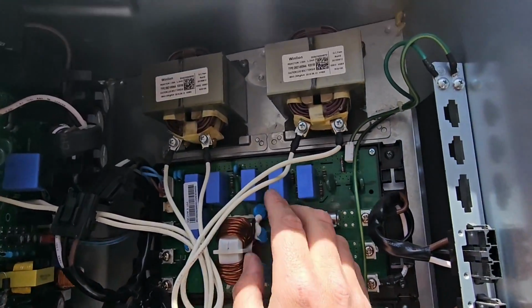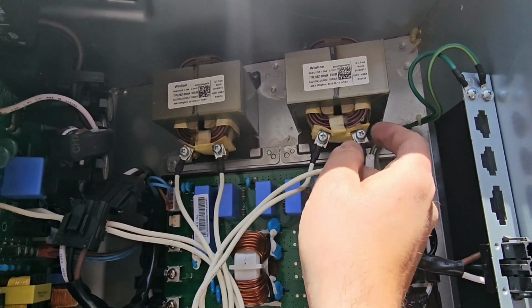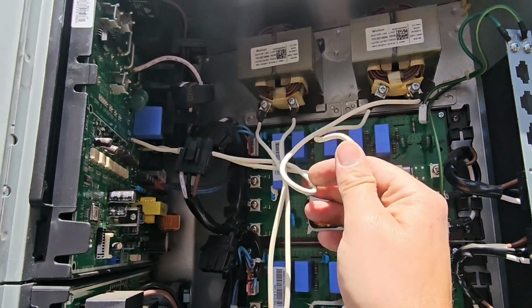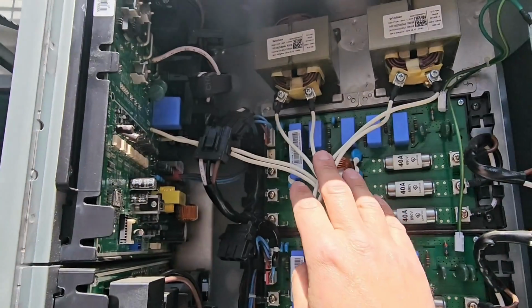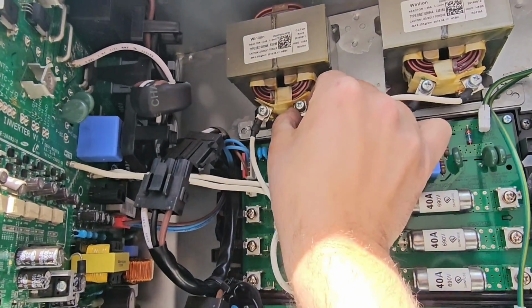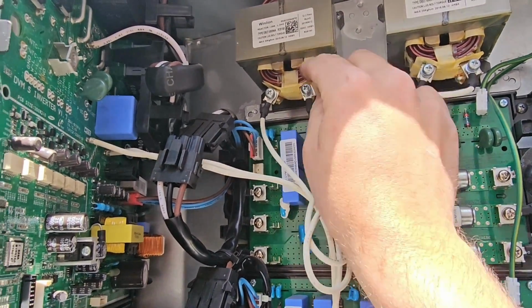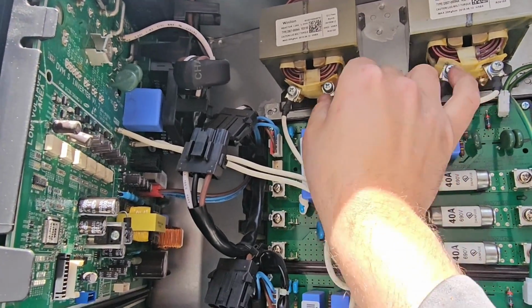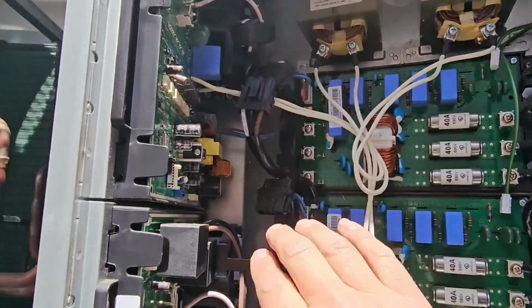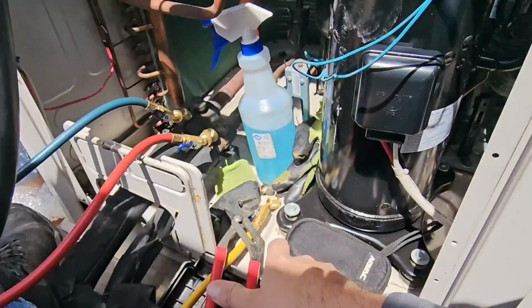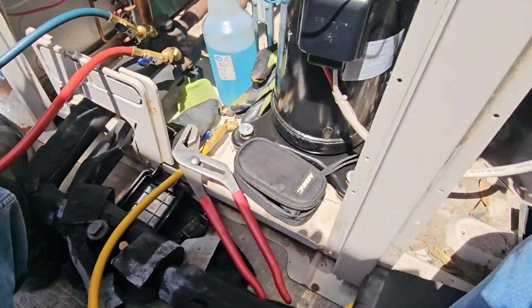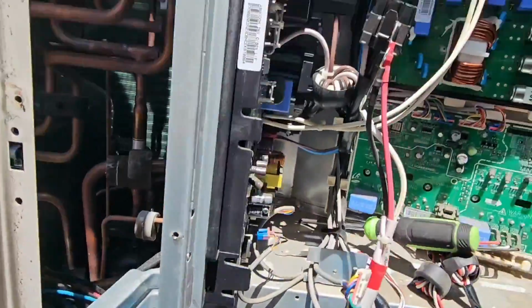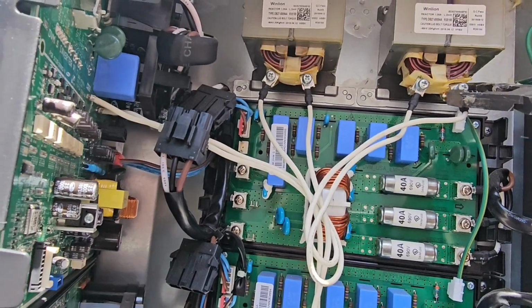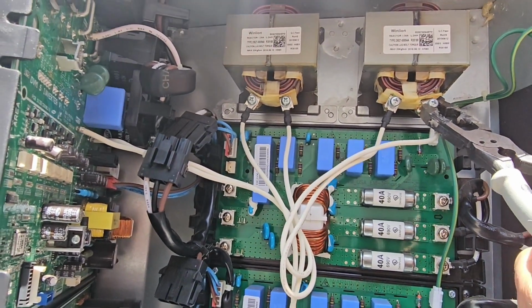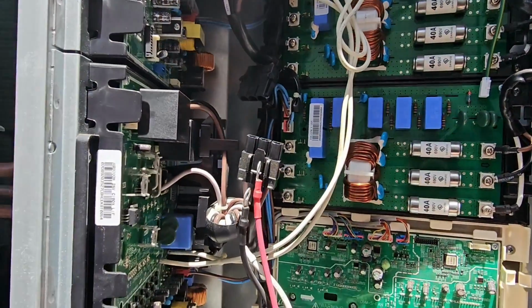You may strip out the head of the screw. Then when you're loosening up these connections on your reactors from the wires that go to your reactors to your inverter board, make sure you hold this right here while you take the screw loose. If you don't, you're liable to break this loose. You don't want to do that. So get something to hold it, maybe a pair of adjustable pliers, maybe some type of clamps, and then just sit there and hold it with one hand, and then take your Phillips screwdriver and loosen that screw with the other.